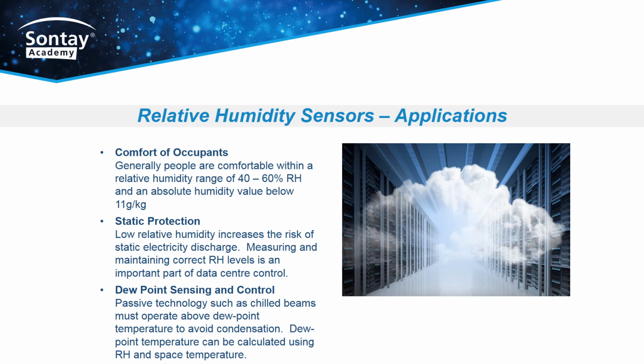Controlling comfort conditions is a key driver for humidity sensing, but there are other applications requiring accurate measurement of relative humidity. The risk of static electricity discharge increases as relative humidity falls. Electronic equipment is susceptible to damage from static discharge, and maintaining the correct relative humidity conditions in spaces such as data halls reduces the risk of this occurring.